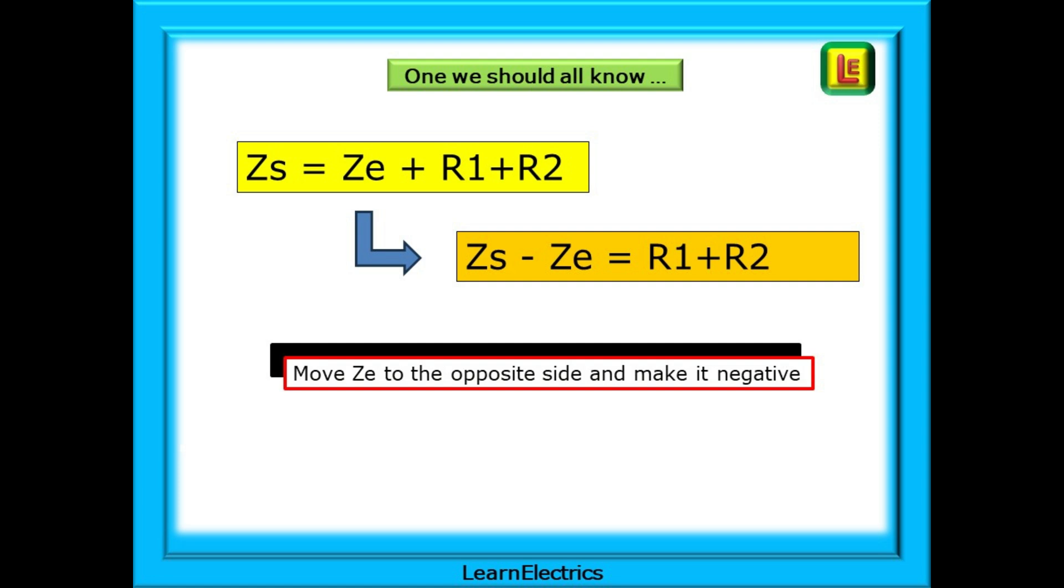And here is an addition formula that we should all know. It will appear in electrical exams so very often. ZS equals ZE plus R1 plus R2. Although ZE doesn't have a sign it is implied that this is a plus value. When ZE moves to the left hand side it changes sign and becomes minus ZE. So we have ZS minus ZE equals R1 plus R2. Essential electrical knowledge.